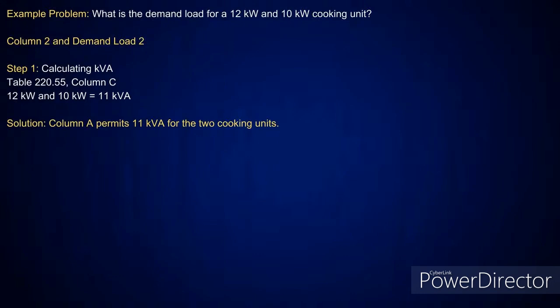So here I've got a 10 and 12. I'm not over 12 kW. So I pick up 2 units, come across, and it tells you it's good for 11 kVA. But if I was below 8 and 3/4, now I've got a different problem. I could have an 8 kW. Now I've got 2 different ones, and I'm going to be looking at using some notes here.